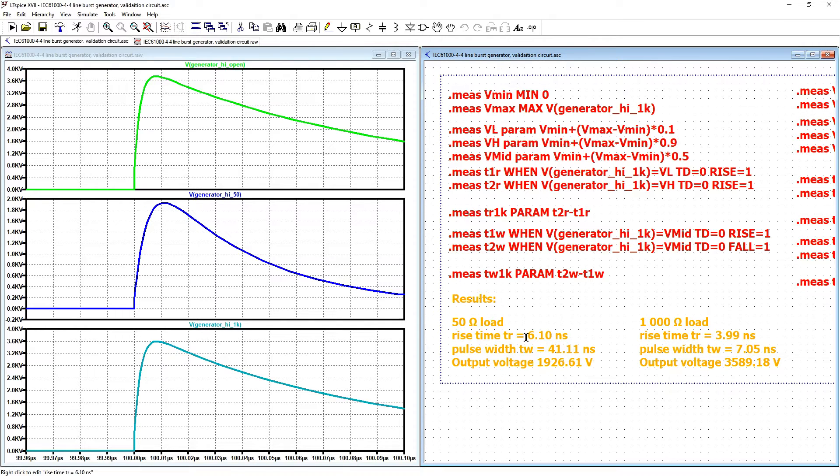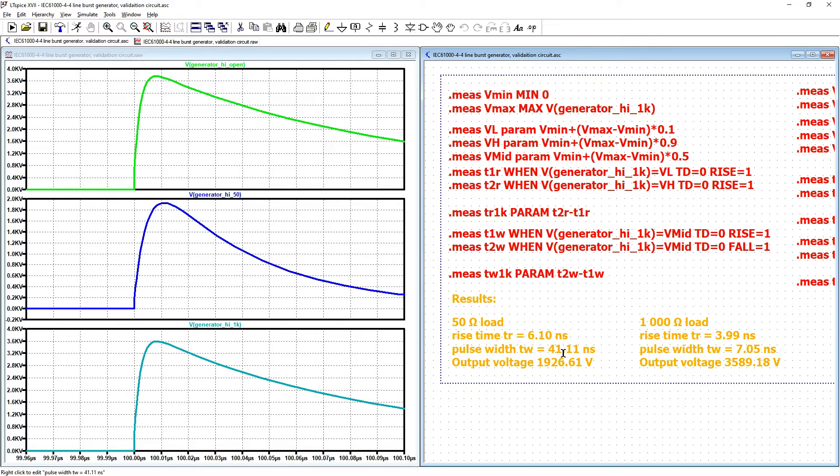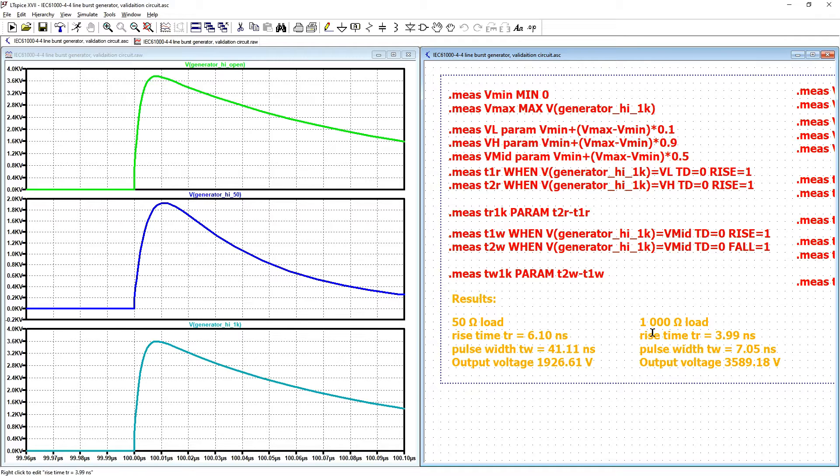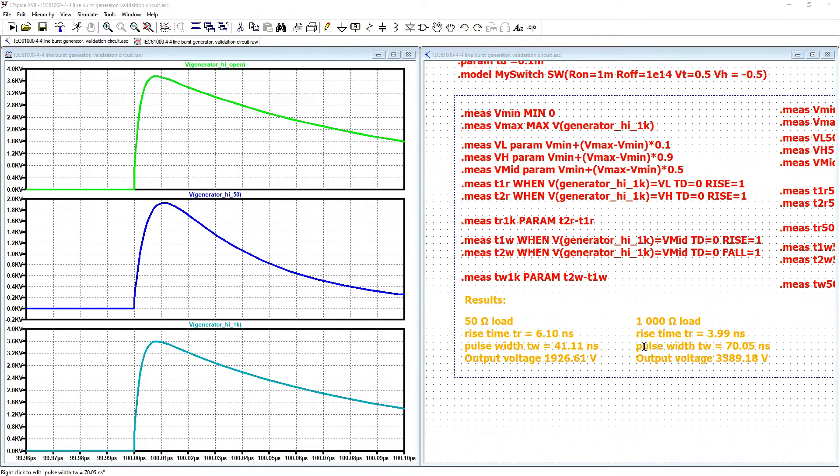The rise time for the 50 ohm load is 6.10 nanoseconds. Pulse width is 41 nanoseconds. Output voltage is close to 2kV because for 50 ohm we should have half of value and now we are at 4kV charging voltage. For 1k ohm load we have rise time almost 4 nanoseconds so different rise time but still in tolerance.